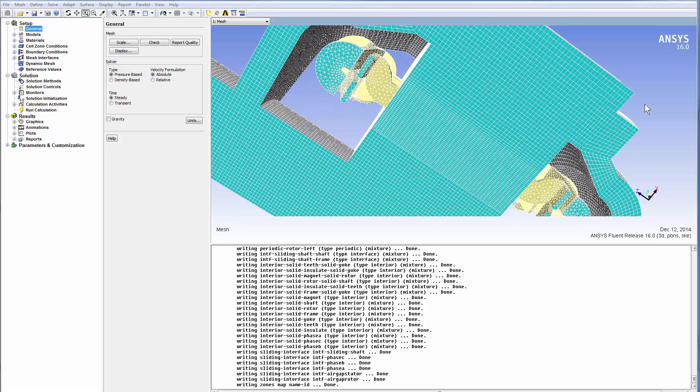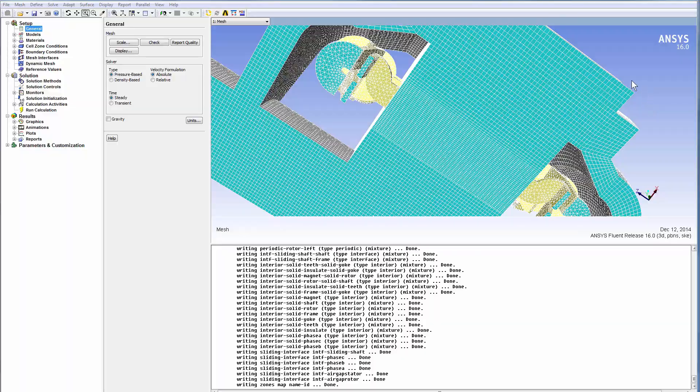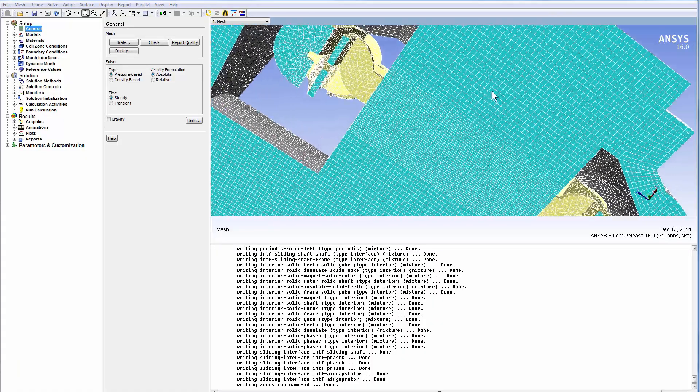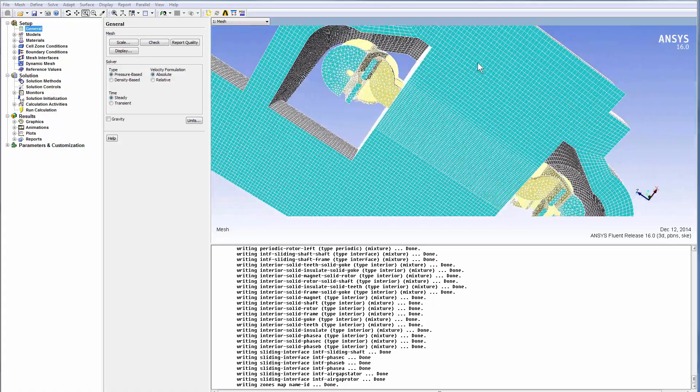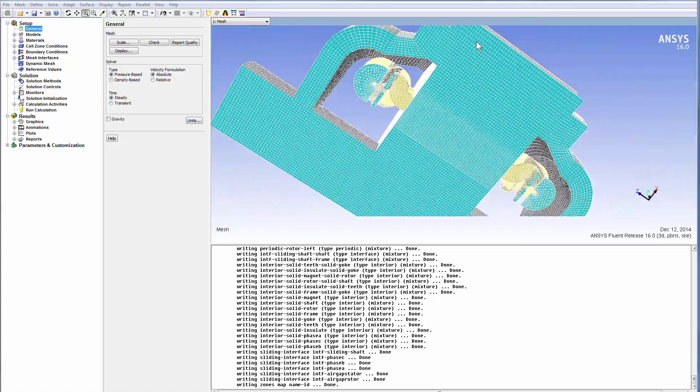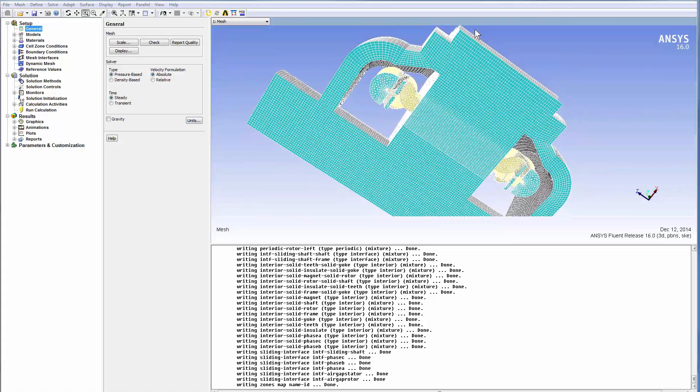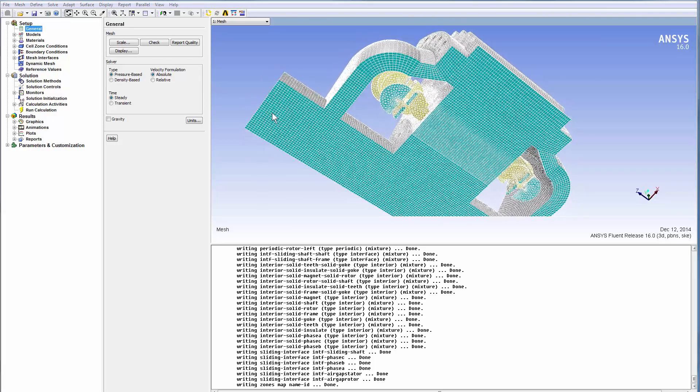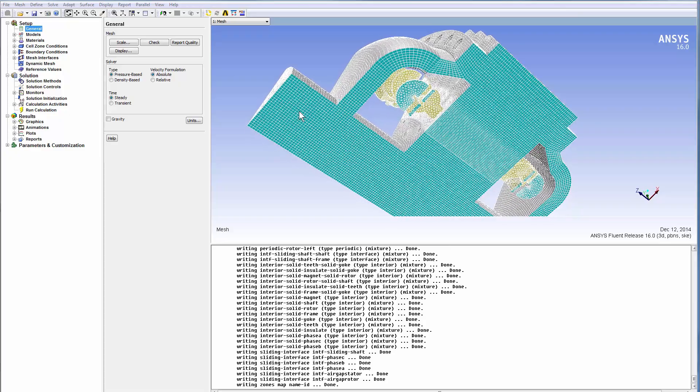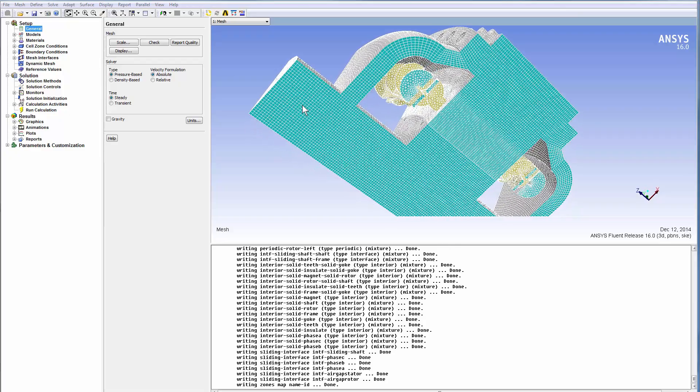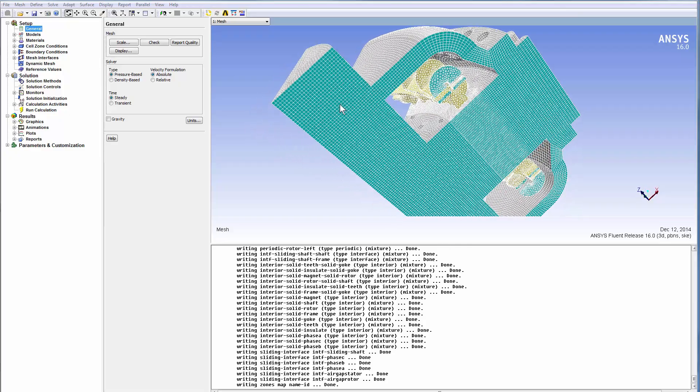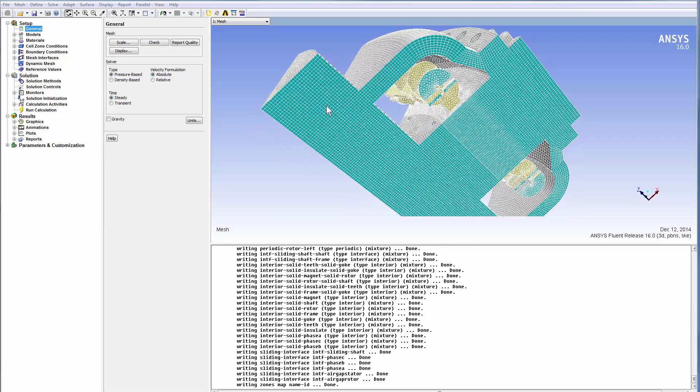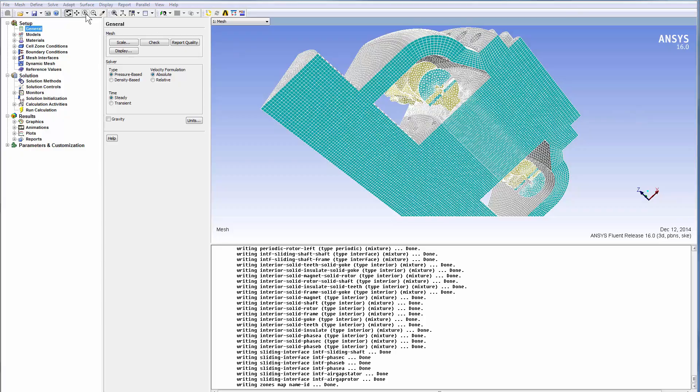Since in CFD we need the details of the end winding configuration, the core of the winding, including liner and insulation layers, touches the ferromagnetic material, which acts as a metallic thermal conductor. The winding transfers the temperature gradient into the ferromagnetic material easier and faster by conduction.